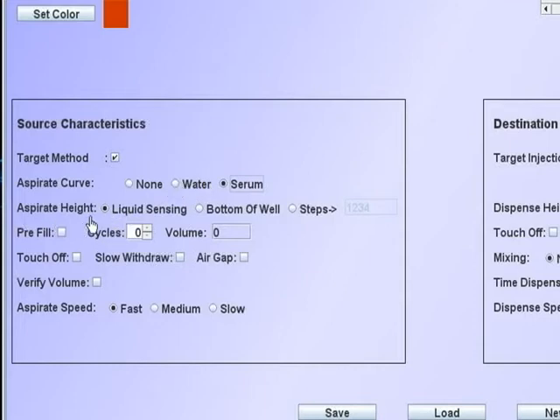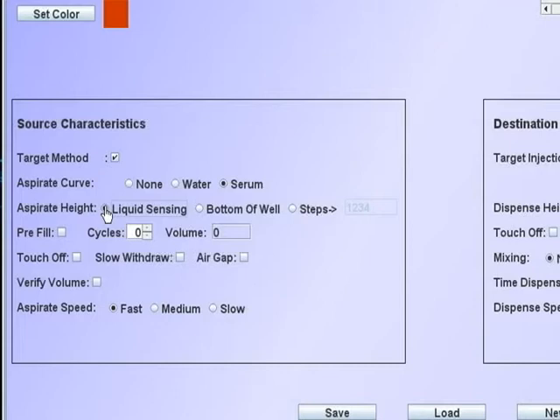Aspirate height determines the tip location for aspiration. If liquid level is selected, the tip will sense liquid level and aspirate a pre-set distance below the sensed liquid level. This is covered elsewhere.